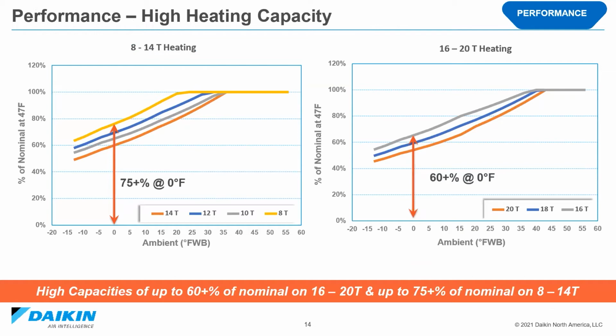With the coil advantages and the newer P-type compressors, the Emerion has higher heating capacities even as the outdoor ambient drops. So for cold climates where, say, heating may be dominant, this is a significant advantage. Now, like the VRV4X platform before it, Emerion is designed for heating down to a -13 Fahrenheit ambient. When you're looking at applications below that, Daikin still utilizes the Aurora platform for heating down to -22.